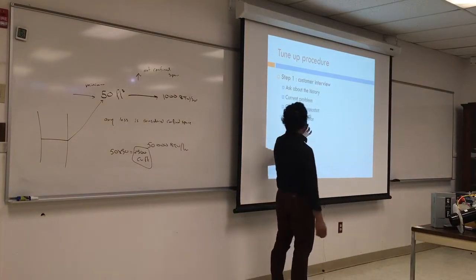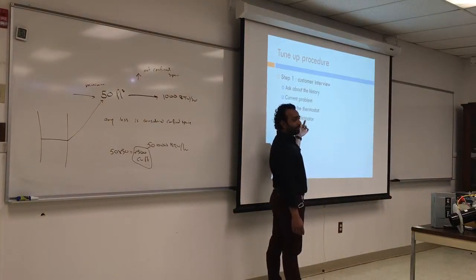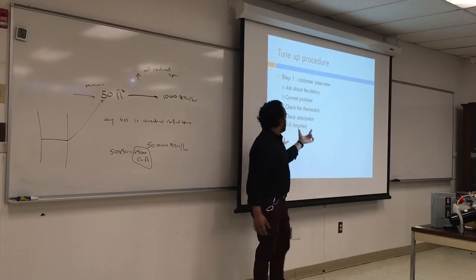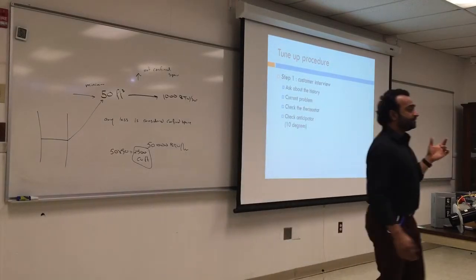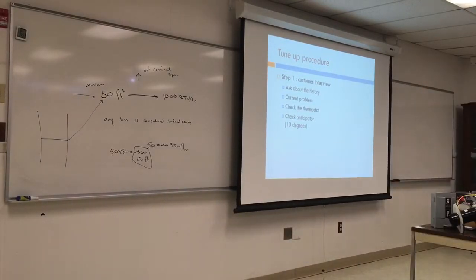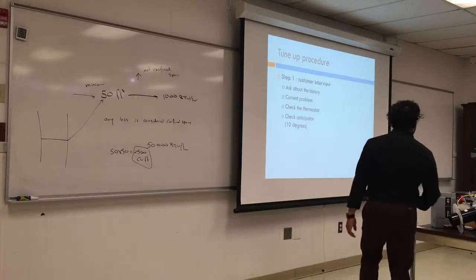Check the heat anticipator. That's something in all thermostats. You don't have to worry about that. The anticipator is in all thermostats. It will make up for the heat produced by the amperage inside the thermostat. So that's something you want to think about.